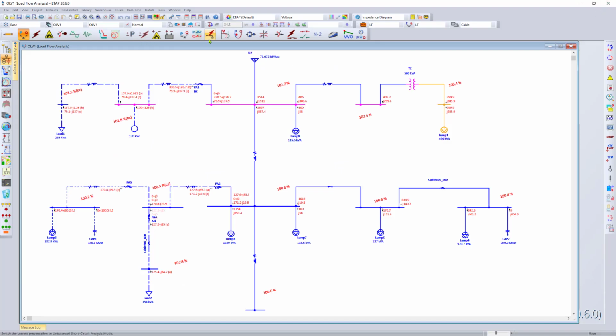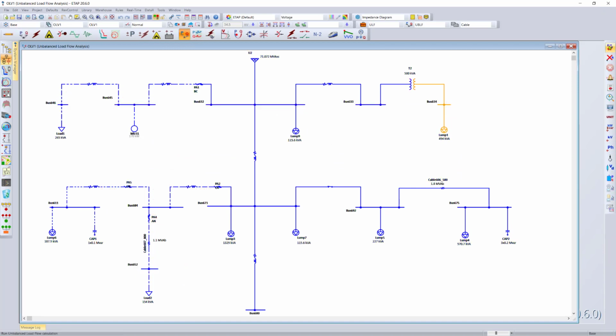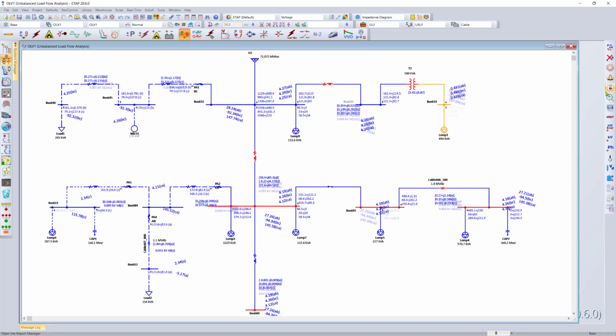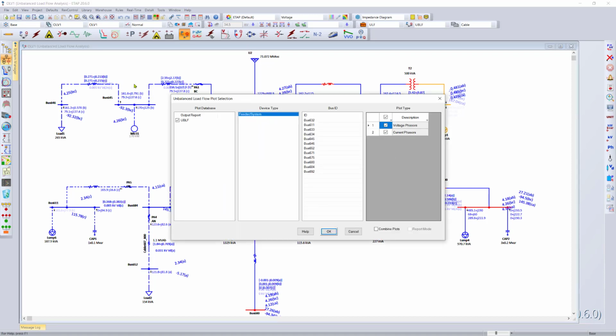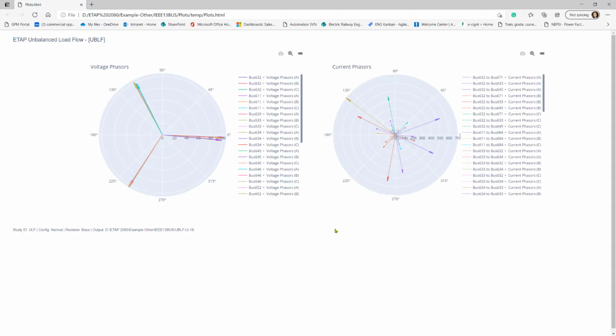With the plot analyzer, you can also go into the unbalanced load flow module, run your unbalanced load flow program, and then bring up the plot analyzer from within this mode. You can then select between a single or multiple buses at the same time and plot the voltage and current phasors. And the program essentially gives you a beautiful tiled view of all your voltage phasors as well as all the current phasors at the same time. And then once again it allows you to interact directly with the diagram and visualize more information.